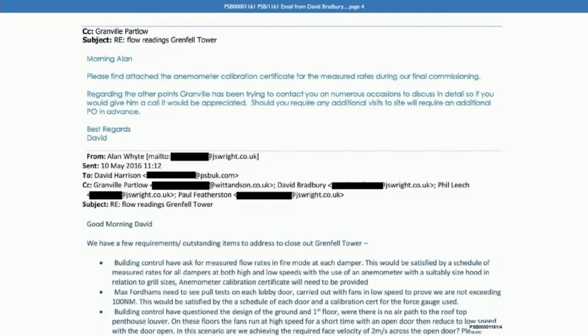So had you been trying to contact Alan White to discuss this point about the force opening, the door force opening? That email is in the context of the grill velocities. The building control had asked could they have volumetric readings for the doors rather than a velocity, but the spec requests velocity, not volumetric. So I asked Alan if he sent me the area of each door, I would work out the volumetric reading in metres cubed per second rather than metres per second. Yes. And no, he never answered any of the requests.